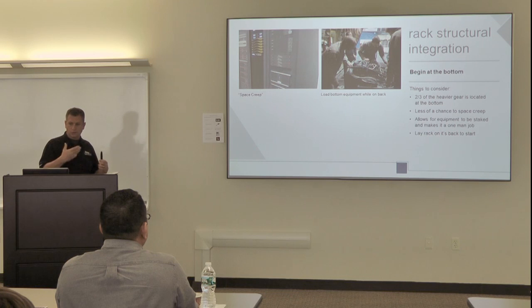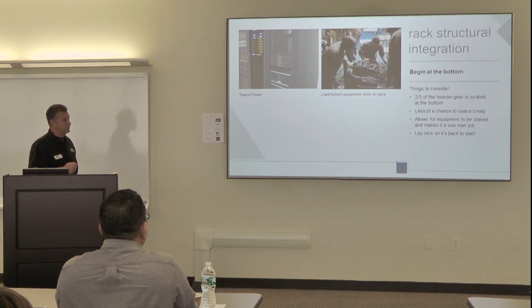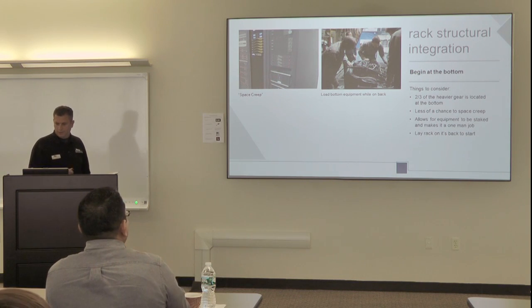When distributing weight, one rule is that two-thirds of the weight should be in the bottom third of the rack. That stops a lot of tipping, and that's the standard a lot of equipment is tested to for weight.